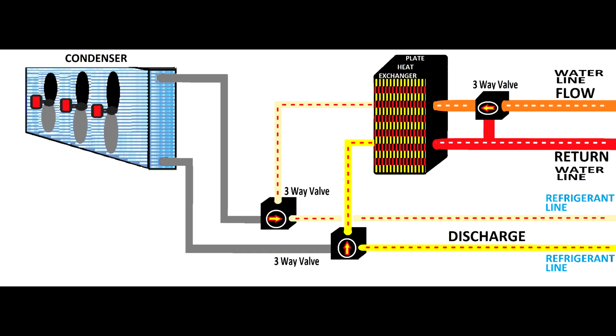Now let's go further and see what happened here. If you remember, I told you that the hot gas which leaves the compressor normally goes into the condenser, and the condenser will eliminate the heat outside. And you see on the condenser we have fans. Normally they are electronically controlled fans or variable speed drive controlled fans, which will run faster or slower according to the heat that needs to be removed from the refrigerant. What we did, we used this plate heat exchanger, and we diverted this hot gas through this plate heat exchanger. Also, the water passes through this plate heat exchanger, which takes the energy of the refrigerant. Actually, the plate heat exchanger acts like a condenser, but the benefit of this is that the hot water, which exchanges energy with the refrigerant, will heat up.